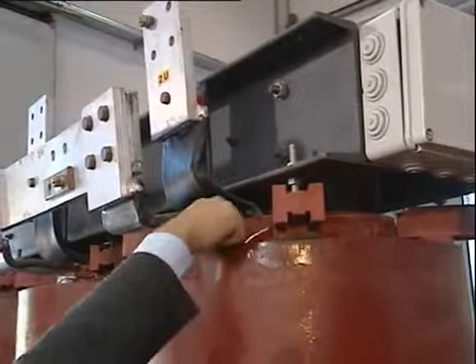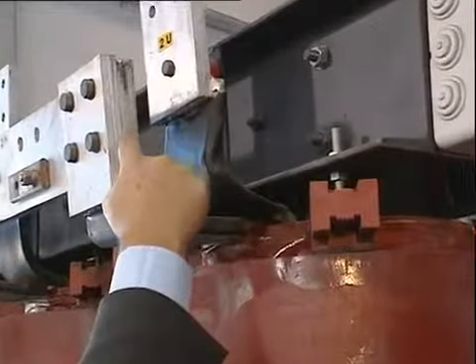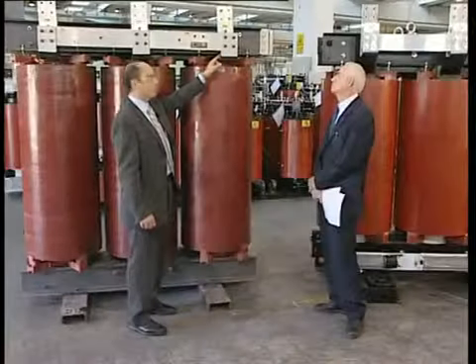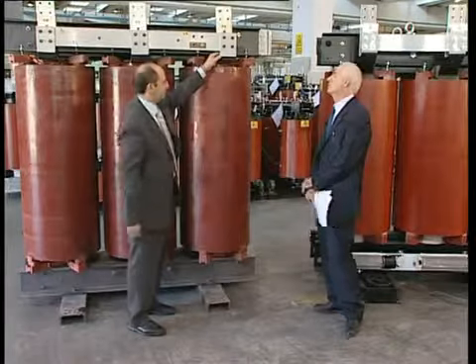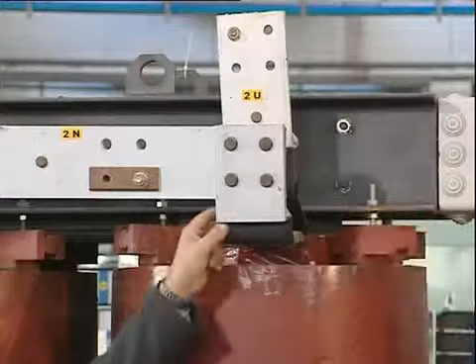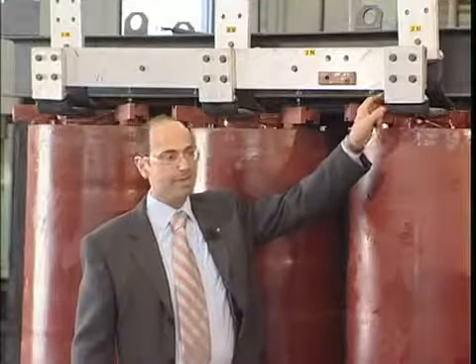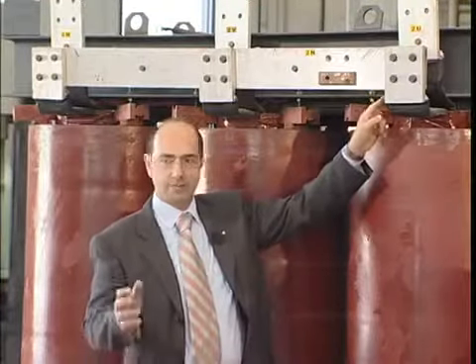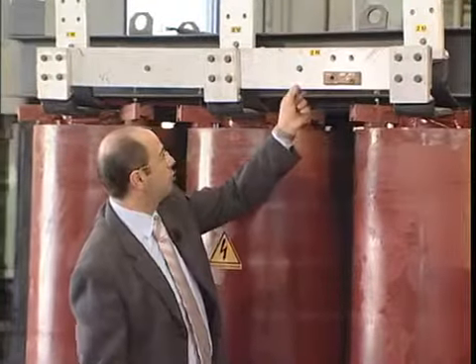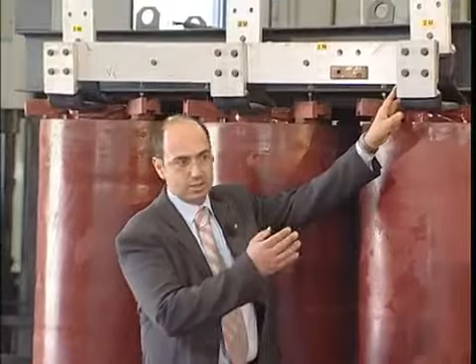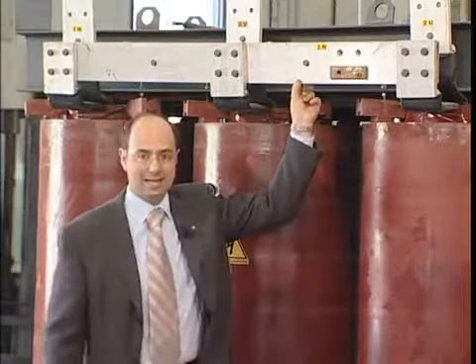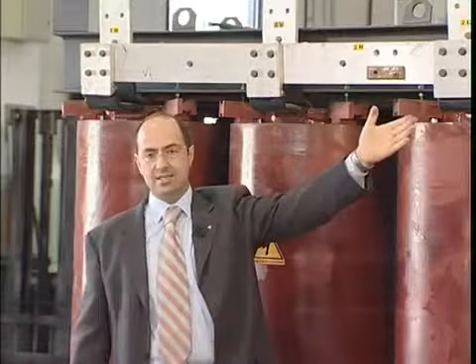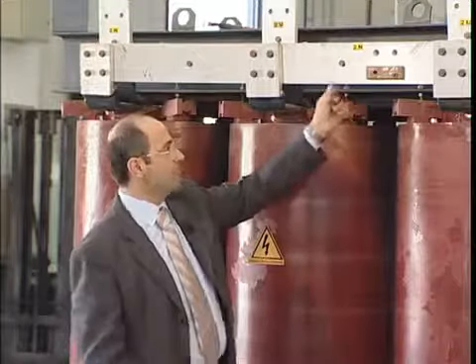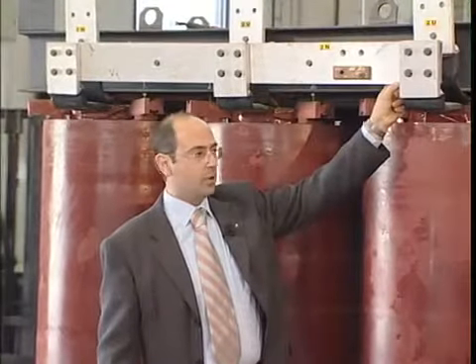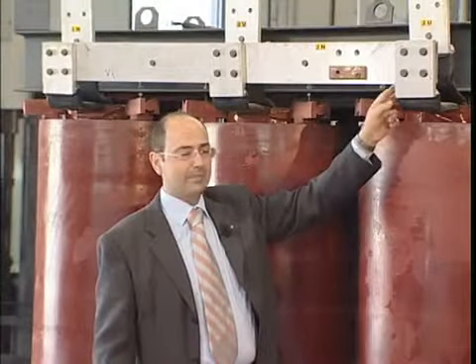Conversely, in our competitor's product, we can notice that a make-do conductor comes out from inside the winding and is then butt-welded on one of the two bars, having the same size as in our transformer. Consequently, here there is an apparent weak spot. A weak point, which is a series welding that, theoretically, is supposed to bear approximately 3,600 amperes. Even the contact with the star center conductor is exactly half ours, although the star center conductor has two bars having the same section as in our transformer. Unfortunately, they have been positioned in the wrong way, to the point that they ensure only half the contact surface.